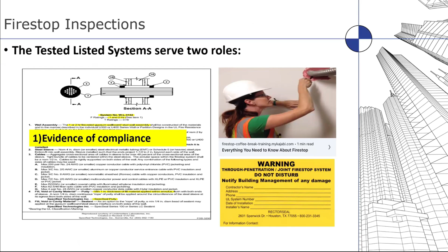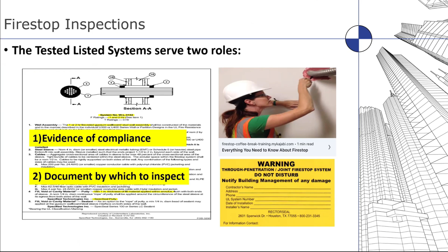So when we inspect fire stops, there are a couple of things this serves for. One is evidence of compliance - we're looking at how we know this fire stop application was done properly, and what document is being used to verify that. You'll see on the bottom right there's a sticker, a label that can be placed on a wall that says this was fire stopped in this method, with this kind of number, and here's who to contact if you have questions. One of the things inspectors look for is to make sure the listing states the types of materials being used.